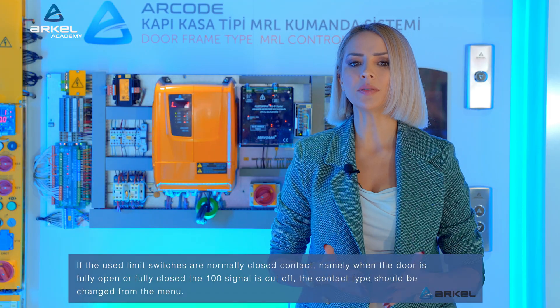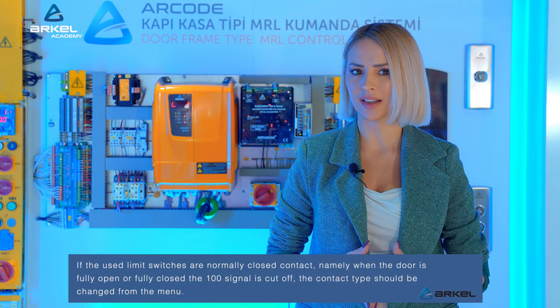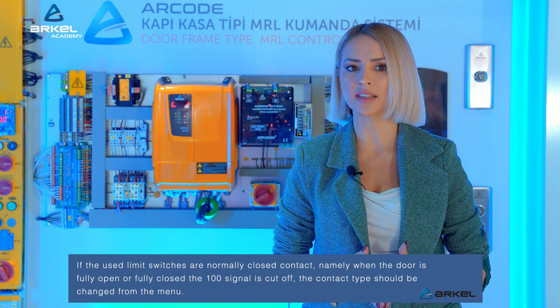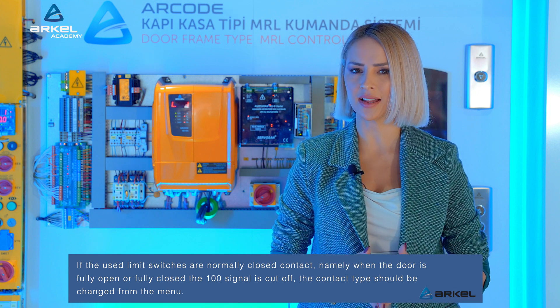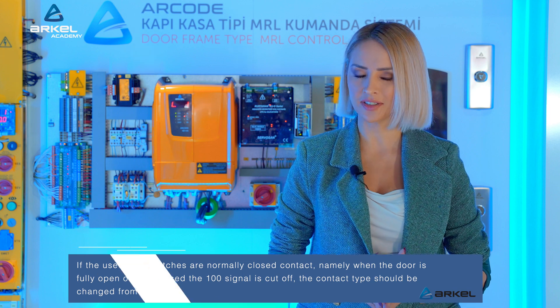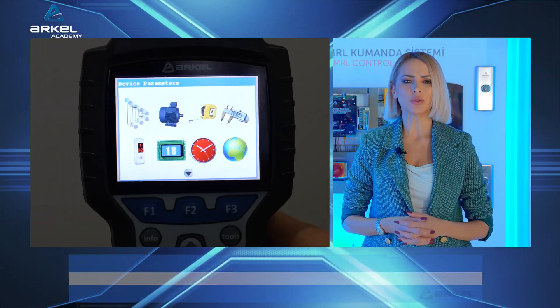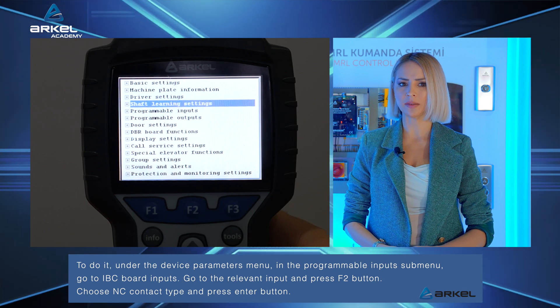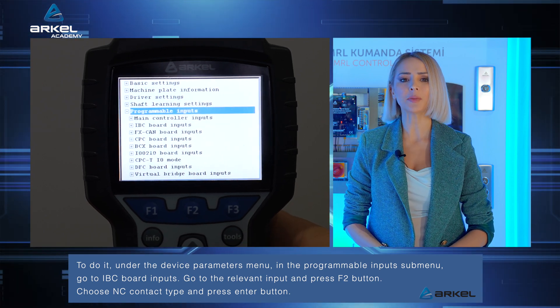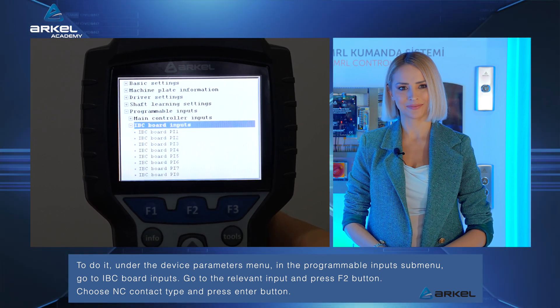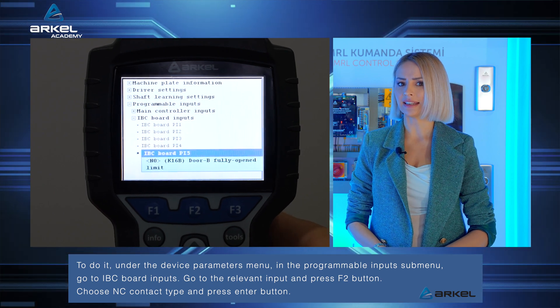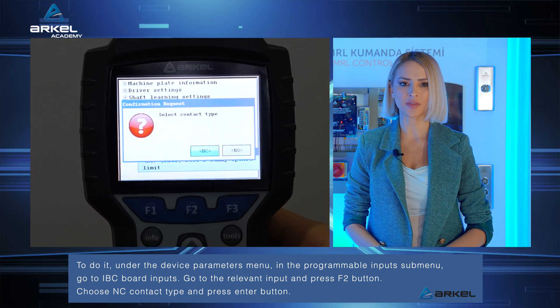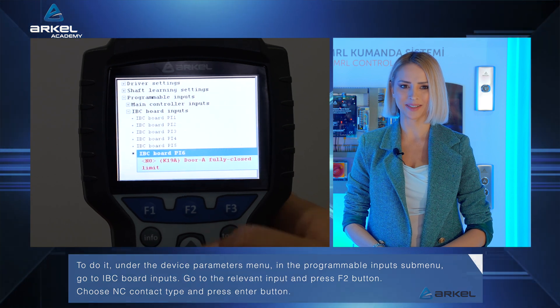If the used limit switches are normally closed contact — meaning when the door is fully open or fully closed the 100 signal is cut off — the contact type should be changed from the menu. To do it, under the Device Parameters menu, in the Programmable Inputs submenu, go to IBC Board Inputs. Go to the relevant input and press the F2 button. Choose NC Contact Type and press the Enter button.